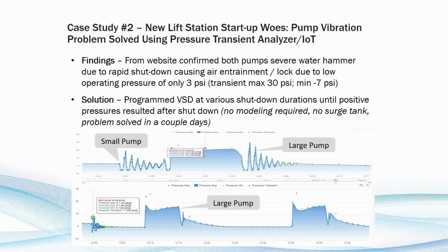So we played around with some of the control logic and had the pumps ramp down at a slower speed, and we did iteration over a couple of days, and figured out that if we just slowly ramp the pump down, we could keep pressures positive. And so you can see in the second chart, the large pump is running and you don't see that pressure transient occurring, and pressures are staying positive, which means we're not entraining air every time the pump shuts down. So this was just a very quick, short duration dialogue we had with engineering and operations, and we were able to resolve the problem very quickly. A lot of water hammer and surge problems require complex modeling. A lot of times we end up recommending surge tanks, but this problem was just solved through operational controls, which is really the best ending you could hope for.